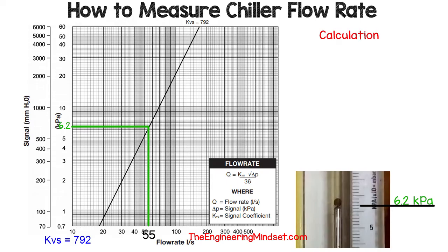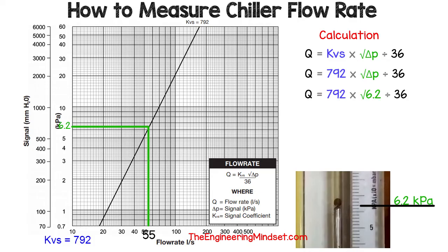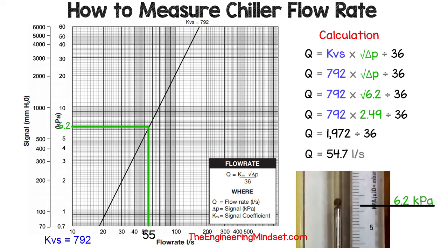For a more precise result, we can perform a calculation using the formula: flow rate Q equals the KVS value multiplied by the square root of the pressure difference, divided by 36. Substituting in our known KVS value and our pressure difference of 6.2 kilopascals, we square root that value, multiply by the KVS value, then divide by 36 to get an answer of 54.7 litres per second. And there you have it — that is the water flow rate for your chiller.